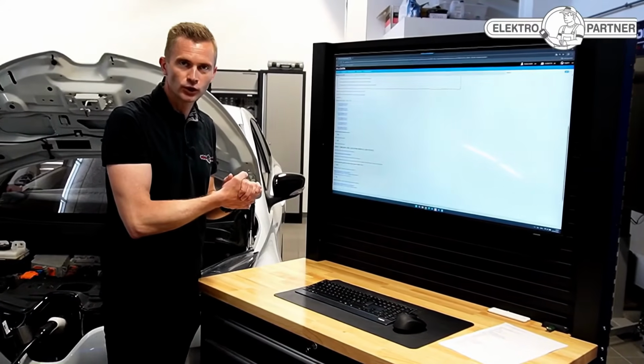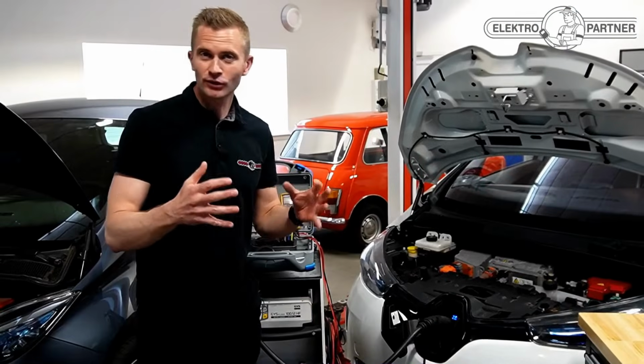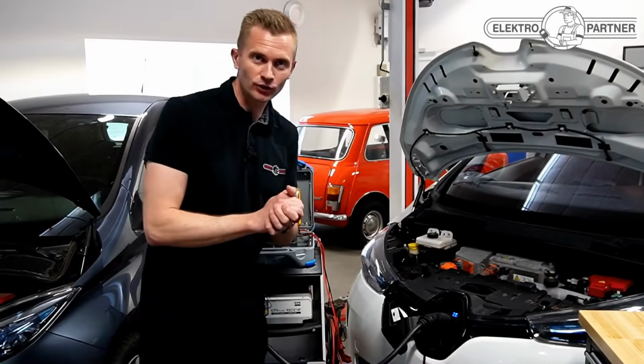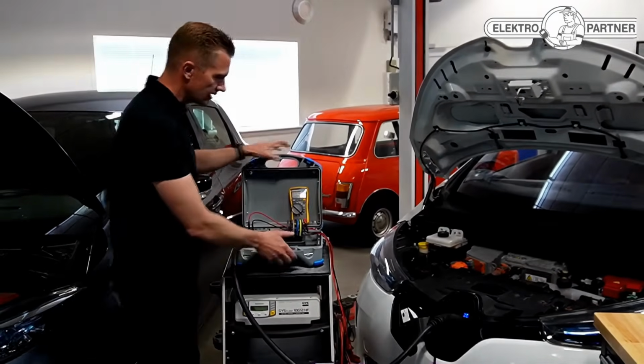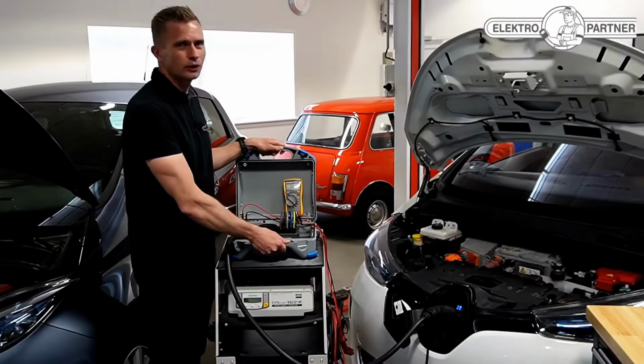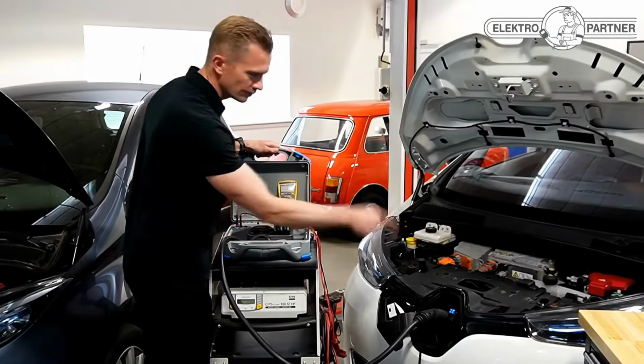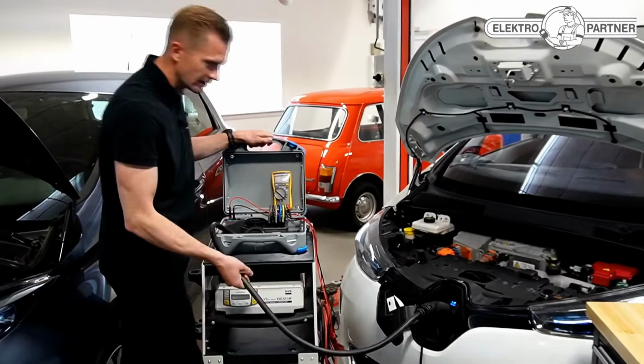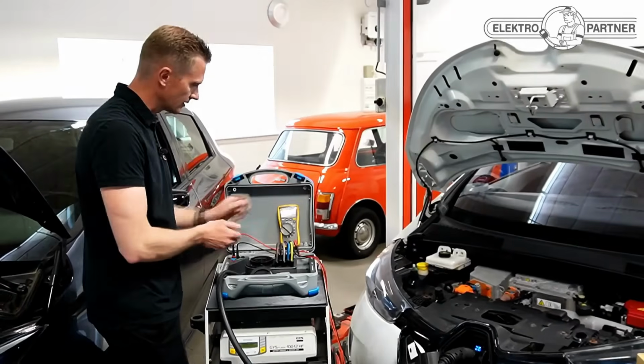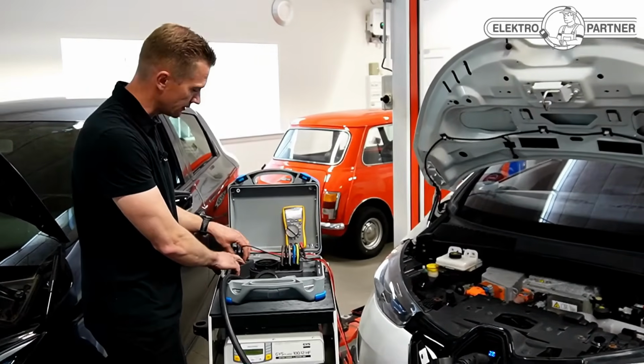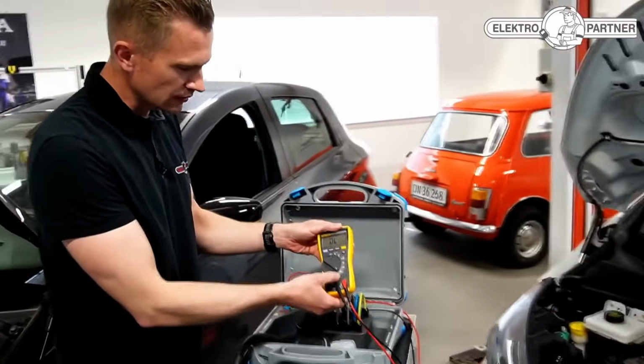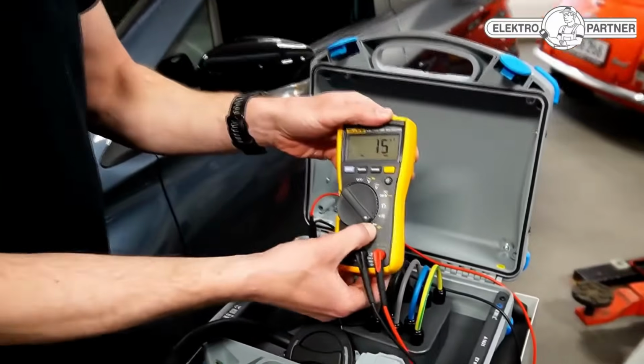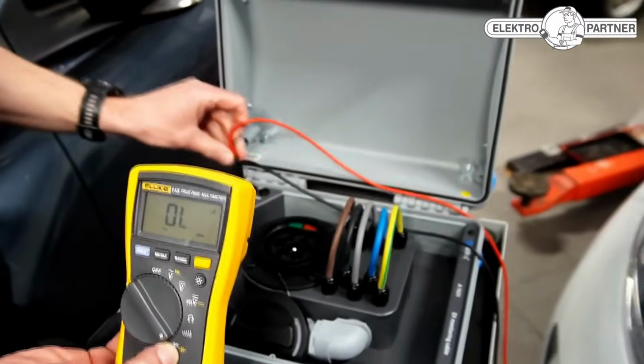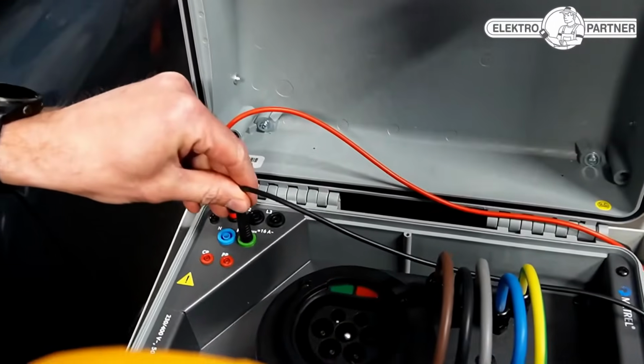That's what we're going to try now. We need to do the first measurement as the manufacturer instructs. I have this breakout box here, which is great for troubleshooting. We could measure at the socket, but using this lets us be sure we're actually on the plug pins. We have a multimeter, and since we need to check capacitors, we select this setting, connected from phase 1 to ground as prescribed.